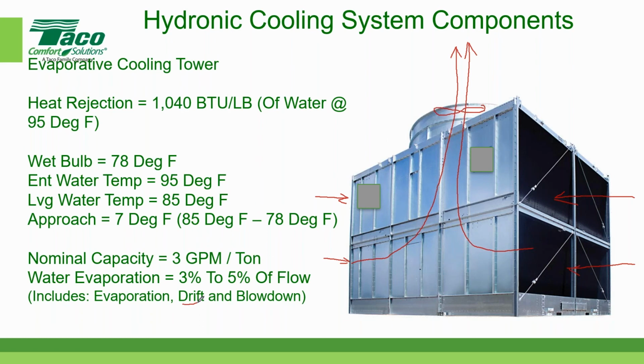Drift is what happens when the wind blows. When the wind blows, it actually strips water off of the cooling tower, and it doesn't get to evaporate and cool the fluid. It just gets wasted by the air that's out there. And cooling tower manufacturers try to design their towers to minimize the amount of water that's lost through drift. And blowdown: when you evaporate water in a cooling tower, what's left behind is sometimes not all that good looking. It can be really disastrous looking stuff, and it collects in the basin of the cooling tower. It can actually turn into mud if it's very severe.